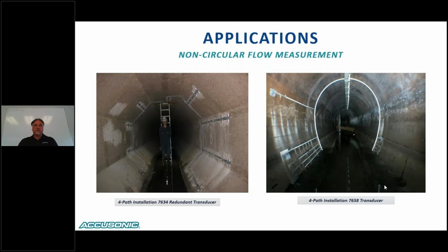Again, this isn't technology that's strictly applied to circular penstocks. Anything that's non-circular, we can measure. As long as we can identify the wetted area, we can measure it. The image on the left is showing our 7634, the redundant transducers mounted directly to the pipe wall. And then again, just the detail on the right showing that we can do horseshoe type tunnels.